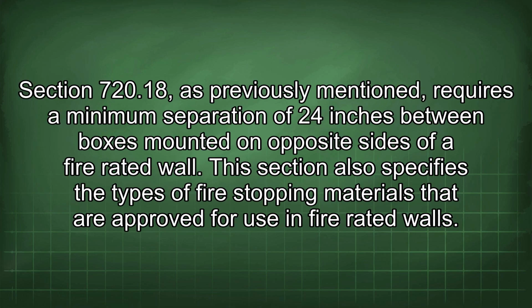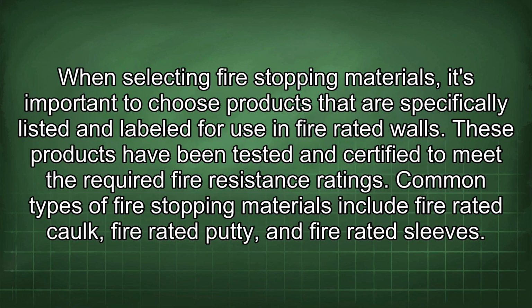Section 720.18, as previously mentioned, requires a minimum separation of 24 inches between boxes mounted on opposite sides of a fire-rated wall. This section also specifies the types of fire-stopping materials that are approved for use in fire-rated walls. When selecting fire-stopping materials, it's important to choose products that are specifically listed and labeled for use in fire-rated walls. These products have been tested and certified to meet the required fire resistance ratings.